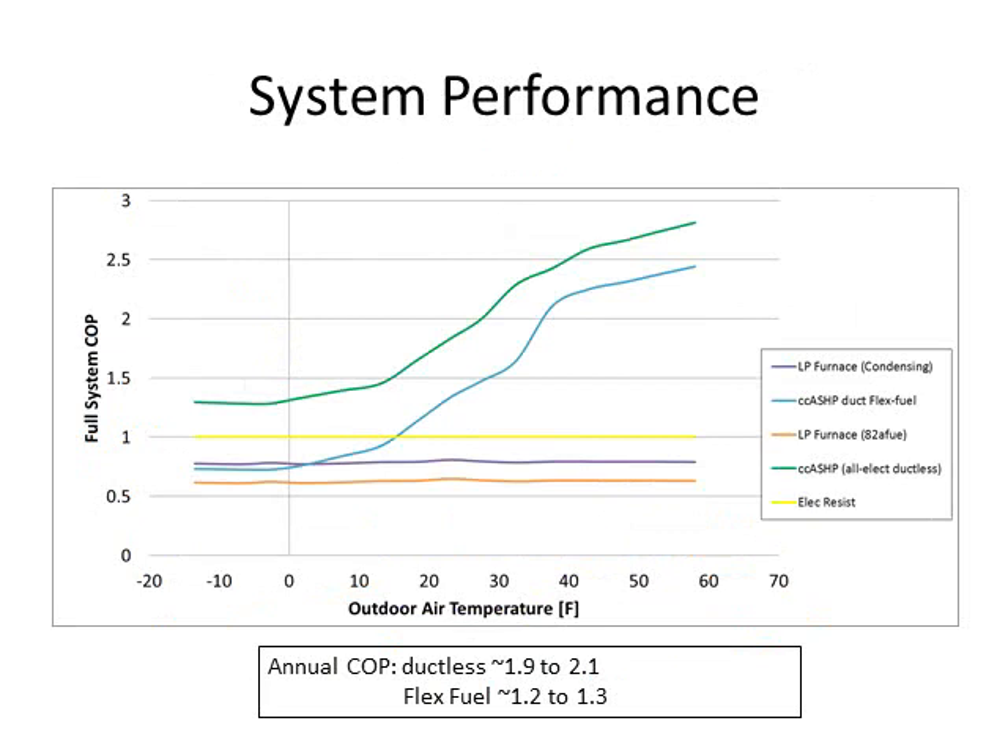This plot compares system performance across different heating systems. The three lines at the bottom — standard efficiency propane furnace, condensing propane furnace, and electric resistance heat — all come in at a COP of one or lower across all outside air temperatures. The two curved lines show two of our heat pump systems: the blue line is the ducted flex fuel system with an annual COP of about 1.2 to 1.3, and the green line is the ductless system with an annual COP of 1.9 to 2.1 — really great performance.